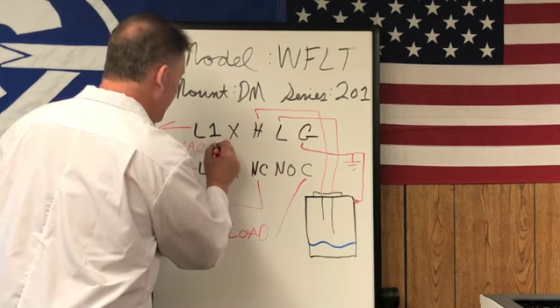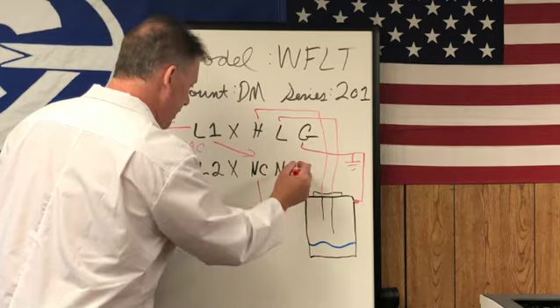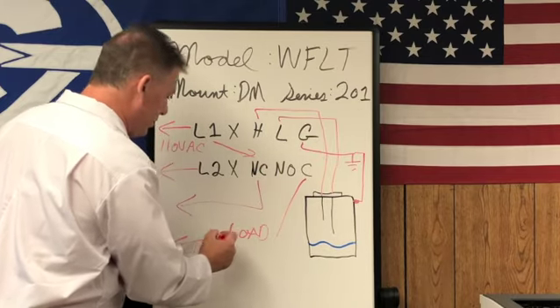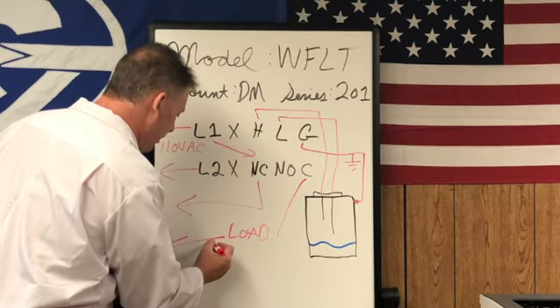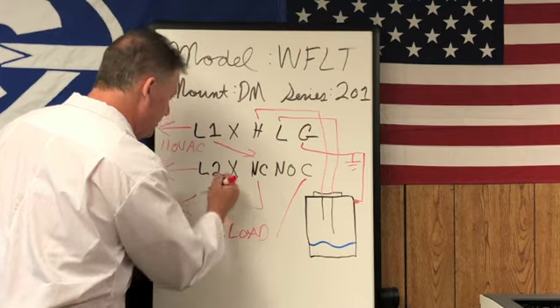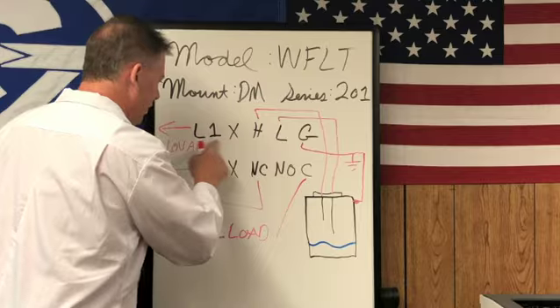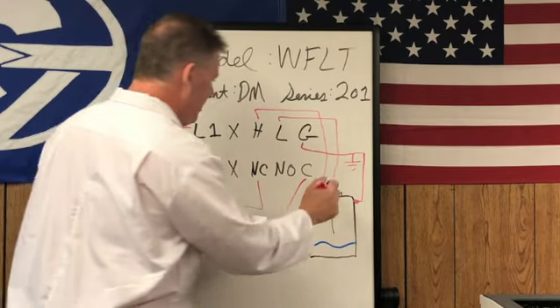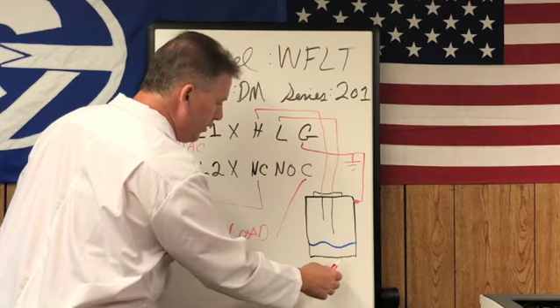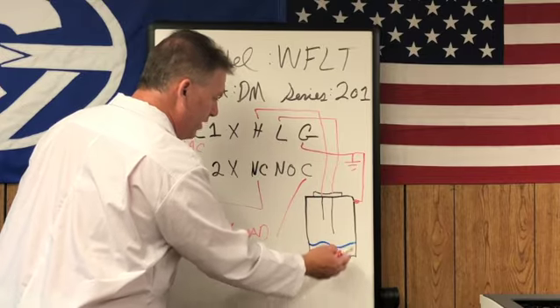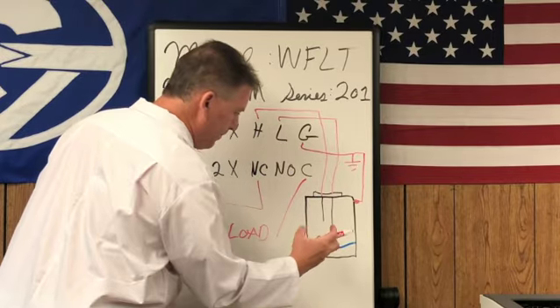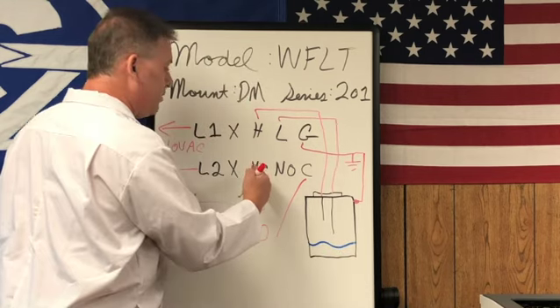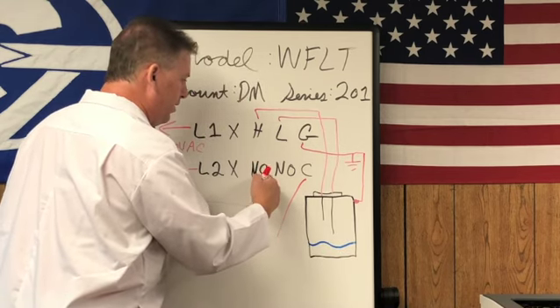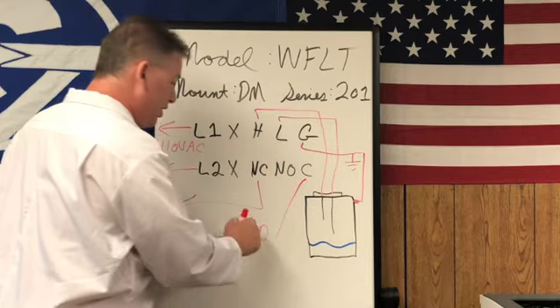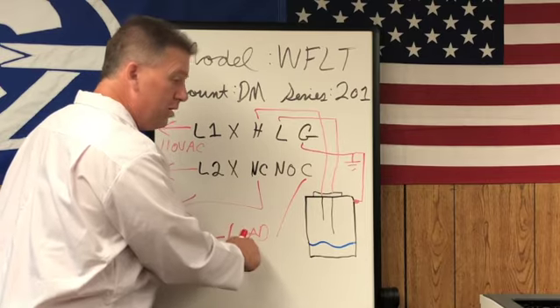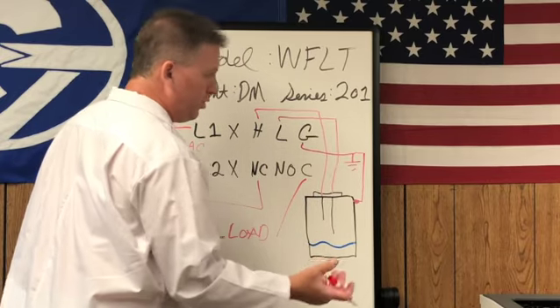You would simply bring L1 to the normally closed. Common is going to go to your solenoid or whatever you're hooked up to, and instead of going back to an external line power, it's going to go straight up to L2, and that will create your loop as well. So here's your water level or whatever product you have in there. When it touches the low probe, nothing's going to happen right now. Then it hits the high probe, and the relay is going to energize. Normally closed will be open, normally open will be closed, and it's going to shut off whatever you have hooked up. It'll close your solenoid, it'll turn your pump off.